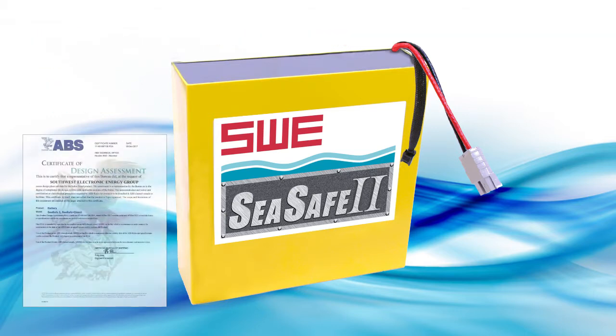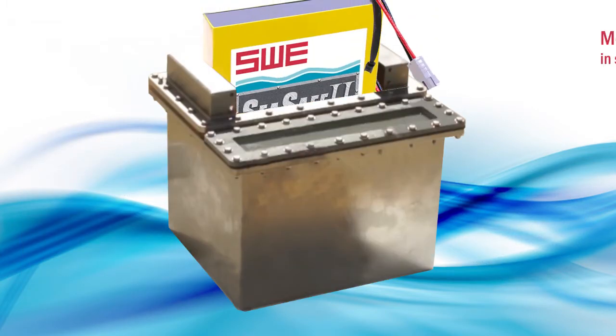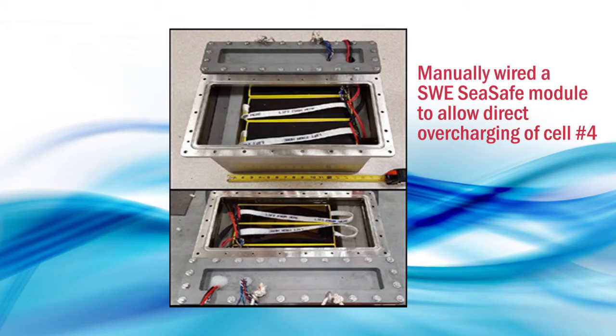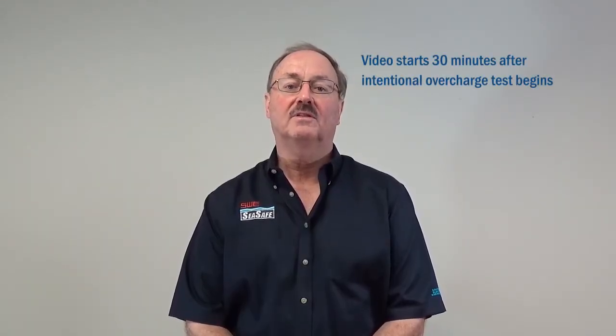Our lithium-ion battery pack is certified by ABS. In our test, we have three SeaSafe modules placed side-by-side in oil inside a stainless steel enclosure. We have wired an SWE SeaSafe module to allow direct overcharging of cell number four, bypassing the battery management system to intentionally induce that cell into thermal runaway. Let's watch the short video segment that begins after 30 minutes of intentional overcharge.